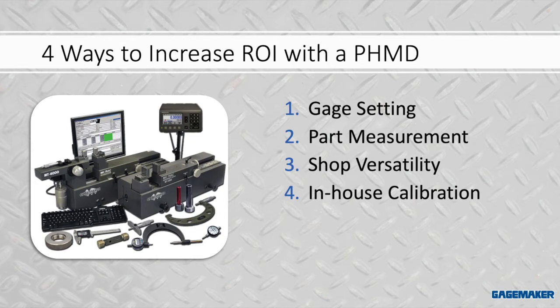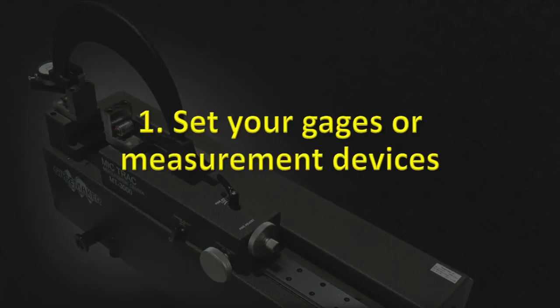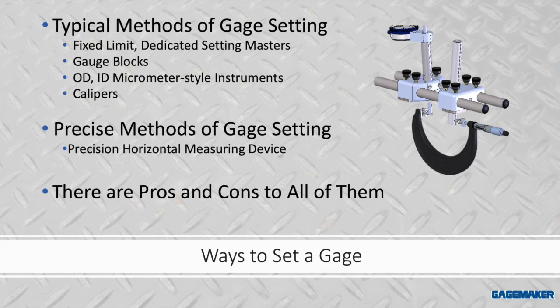No other benefit is as invaluable as this one. Every instrument calibrated in-house saves time and money, and all that goes straight to the bottom line. So common industry-wide practices for presetting, setting, or standardizing hand gauges is to utilize tools that are typically available in the shop. So these may include OD and ID mics or micrometer-style gauges. Gauge block stack-ups are very popular, or Joe blocks, calipers, and then of course dedicated setting masters or fixed limit gauges.